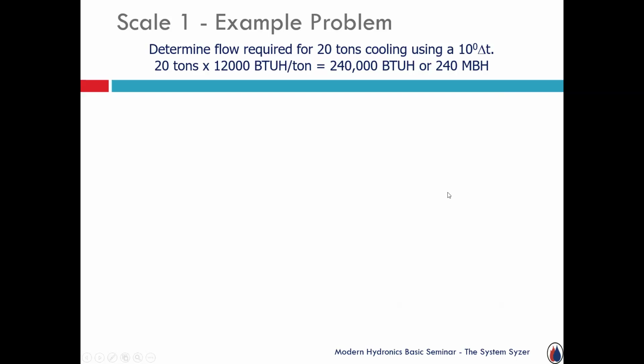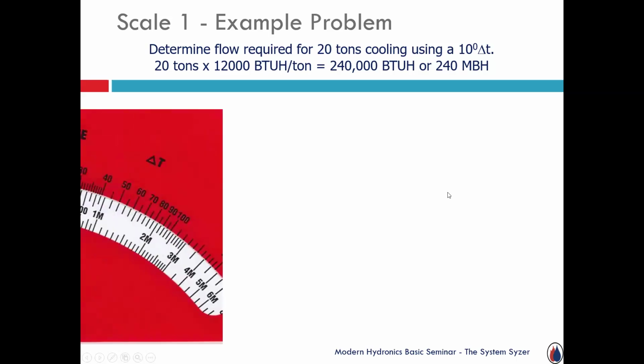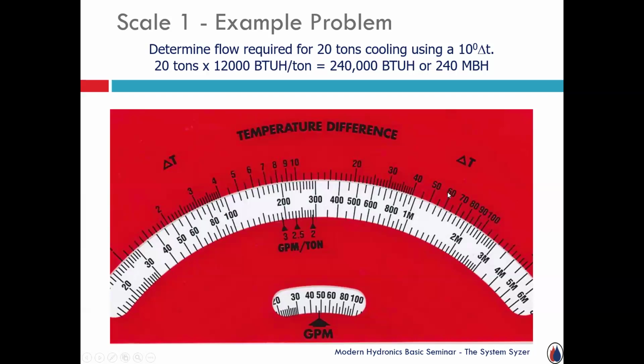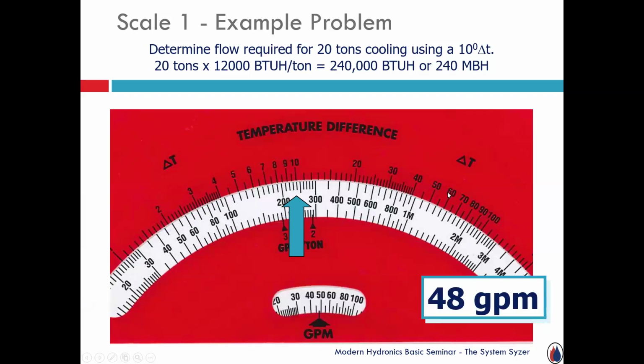Well, I keep saying heating. Here's a quick example for cooling. Determine the flow required for 20 tons of cooling. In this case, we're saying we're going to design it on a 10-degree delta T or a 10-degree temperature rise. So real quickly, in the industry it's kind of known that it's about 12,000 BTUs an hour per ton. So one quick way to calculate it would be 20 times 12,000 is 240,000 BTUs or 240 MBH. So I could take, again, scale 1, find the 240 MBH right here, 10, 20, 30, 40, and I'm going to line it up opposite my acceptable 10-degree temperature rise in this case, and I look at the small white window and it's about 48 gallons a minute. So on a chilled water application, 20 ton, 240,000 BTU load, 48 gallons a minute.